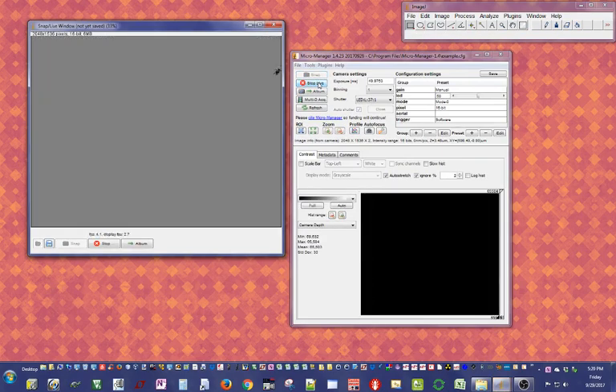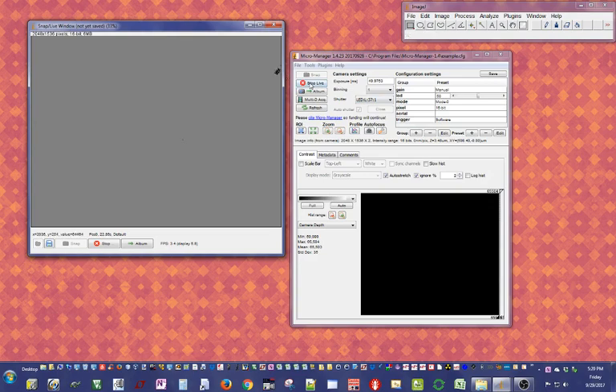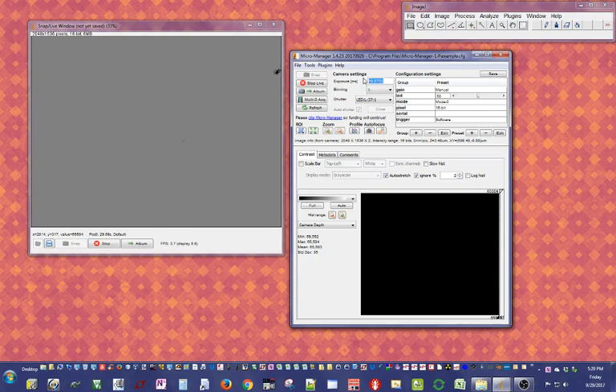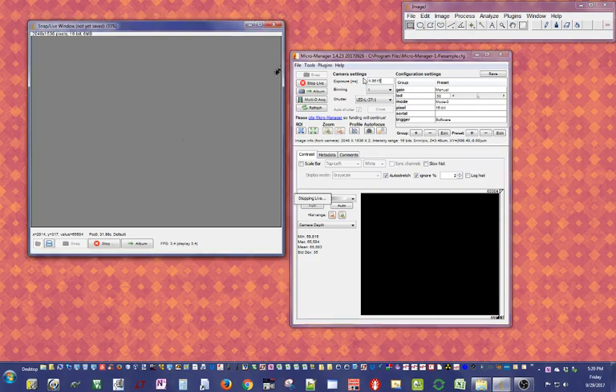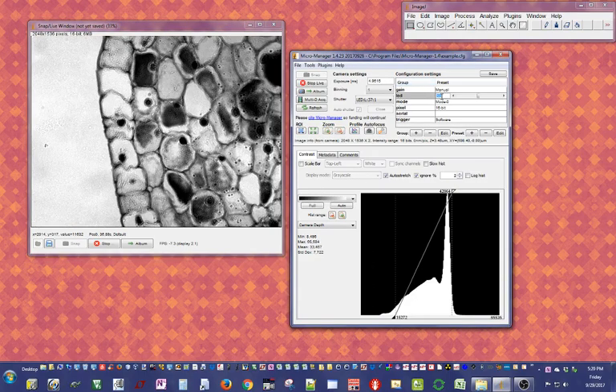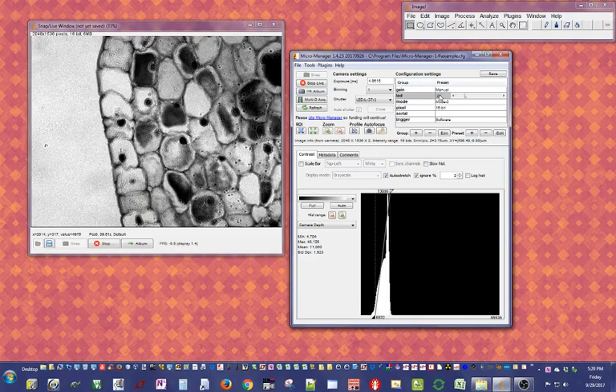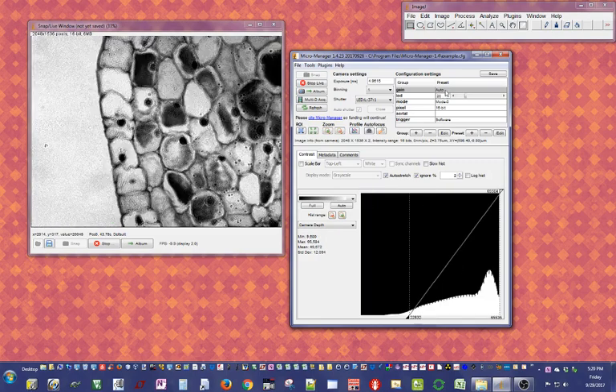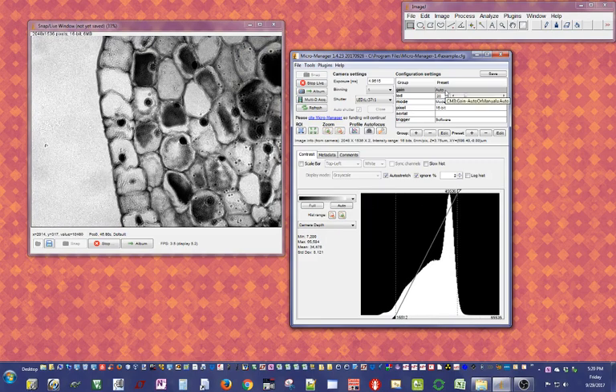The plugin doesn't have that much control of the camera — it can set the trigger mode, it can capture images, but it doesn't have any other control of the camera. So before you launch the plugin, use the live view and make sure the video from the camera looks good. Here the image is pretty saturated, so I'm going to reduce the exposure time, also reduce the LED illumination intensity, and run the gain at auto.